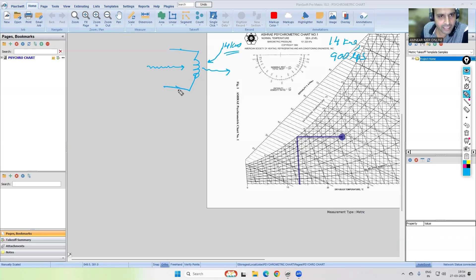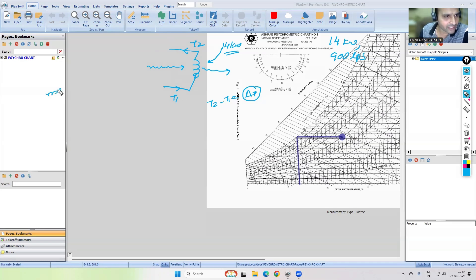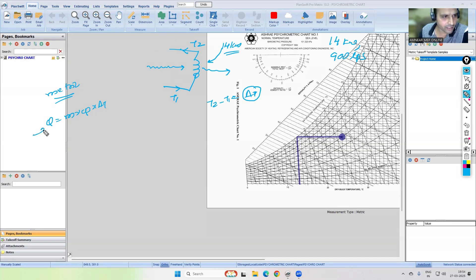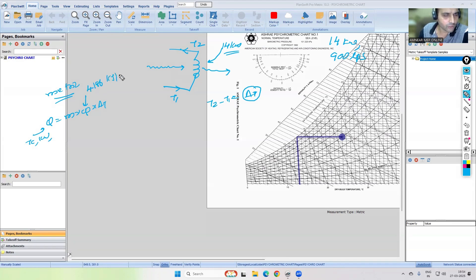If it is a chilled water coil, the supply temperature might be T1 degrees Celsius and the return temperature T2. So T2 minus T1 gives you a delta T, and by using this delta T we calculate the chilled water flow rate. For metric standard, the equation is Q = M × Cp × ΔT, where Q is the total coil load in kilowatts, Cp is the specific heat of water at 4.186 kJ/kg·K, and M is the chilled water flow rate in kg/s (which equals liters per second for water).